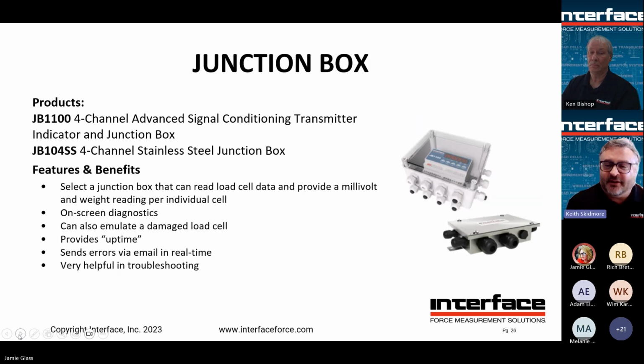Junction boxes. A lot of times you might have multiple points. You had like 4 points underneath the crane. Example, you had load cells, so you're measuring the total weight of the crane and the items being lifted by that crane. You may want to sum those together and just get a single load. Junction box can do that.